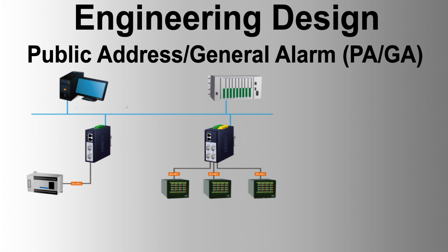The PA-GA philosophy: distribute alarm tones, visual alarms, pre-recorded messages, emergency voice messages, and routine voice messages via loudspeakers and beacons. Areas with high ambient noise levels will use flashing light beacons. Alarms are initiated manually from paging panels or automatically from fire and gas (F&G) detection systems.